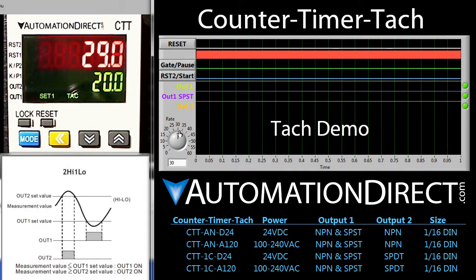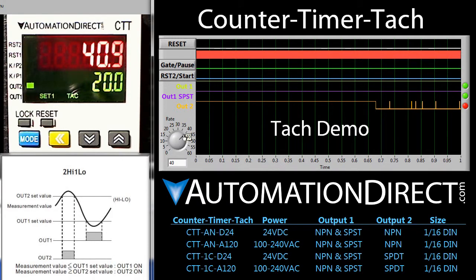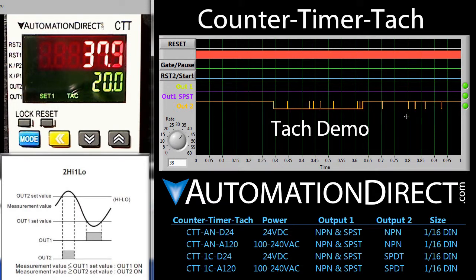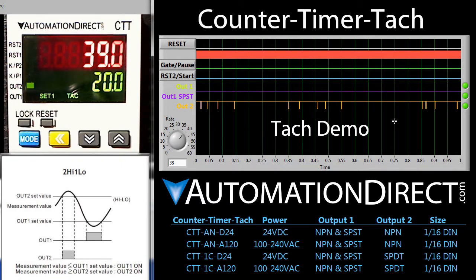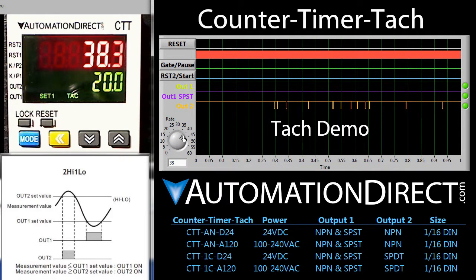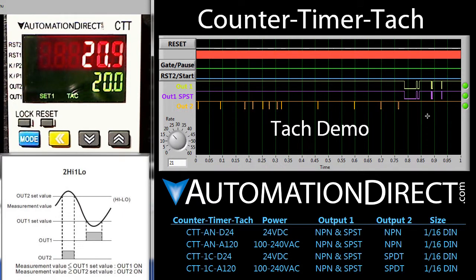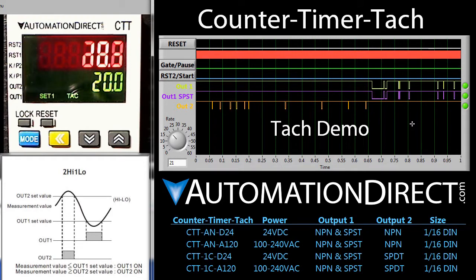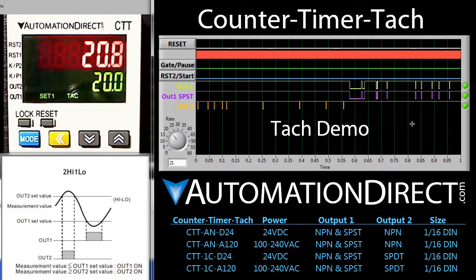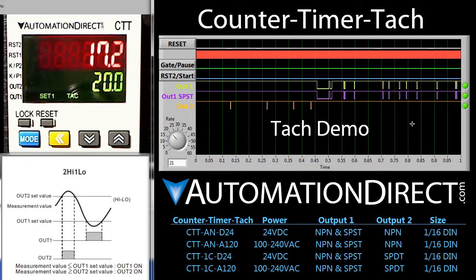So we're at 30 – our set points are 20 and 40. As we get close to the 40 set point – let's put it like 39 or 38 – you can see we get these intermittent responses – it's actually varying up beyond 39 and 40 cycles per second – that's how unreliable the PC signal is. Let's come down near 20 and put in like 21 – and sure enough output 1 is telling us that on the low end it's just as unreliable. So you can see how important it was to have that averaging turned on – that's a really handy feature to have in this counter timer tach module.